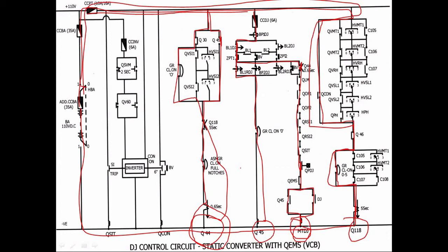Now after a few seconds, that is after 10 to 12 seconds, since DJ is closed, supply from battery via CCINV fuse, since QSVM is in de-energized condition, its normally closed interlock is closed. Since DJ is closed, QV60 is de-energized. So from both the paths, 110 volt supply will come to the static converter and the static converter LT circuit gets energized and the static converter starts functioning.